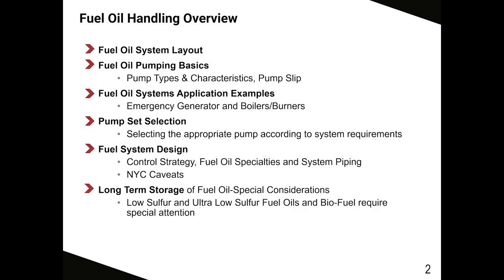A couple of points here is on strategy. There's a large range that we can discuss at future times. And also when we talk about low sulfur fuels and ultra low sulfur and bio, there's a lot of water in those molecules, Ed, right? So yes, you have to pay close attention to how much storage you have in the facility, and the realization that you really do want to filter. You need to filter and polish and dewater it, because those old high sulfur fuels had a biocide in them. The new low sulfur fuels do not.